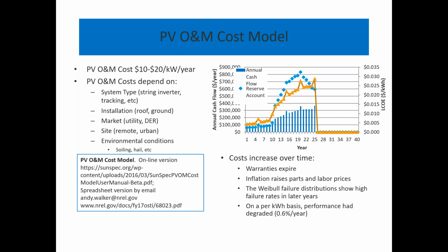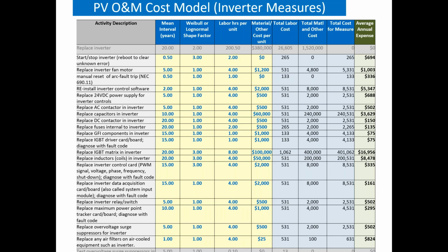Within that cost model, the cost each year is developed by adding up 150 measures. I took all the ones related to inverters and put them on this slide, so you can see on the left the activity description of everything that needs to be done — start and stop or reboot the inverter, replace inverter fan motor, manual reset arc fault trip — with their mean interval, like the Weibull beta factor, and their shape factor, like the Weibull alpha factor.